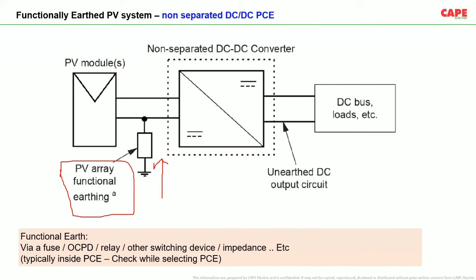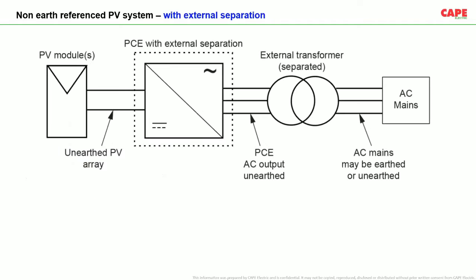Once the functional earthing is disconnected, say for example, this functional earthing is disconnected, under that condition your entire system is floating. In a floating system, a single fault does not create a hazard. So that is the technique which is applied in a functionally earthed system.